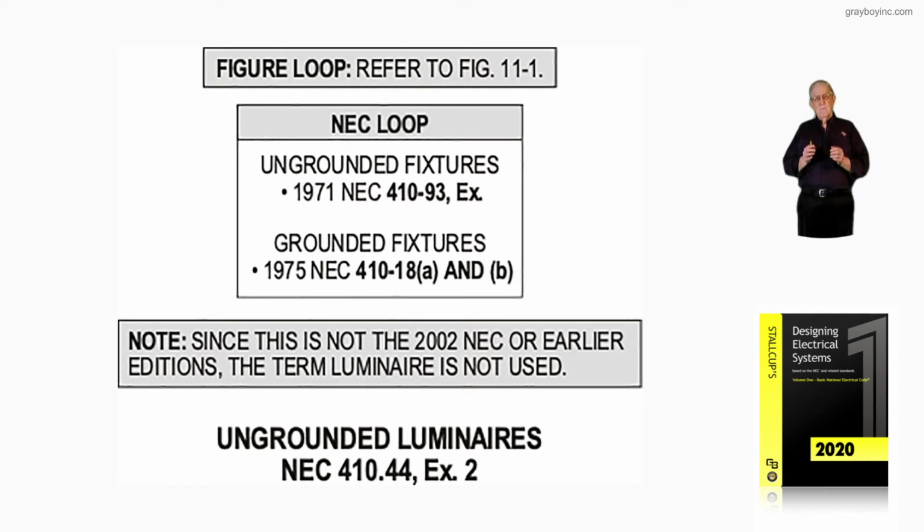So you can see that in past codes from 1971 and back, there were times when two-wire systems were run without an equipment ground and fixtures were installed. So this is the predicament that puts electricians in today when they're replacing lighting fixtures that are on a system that doesn't have an equipment ground routed with the ungrounded conductors. So these Figure 11-1 and 11-2 deal with such a condition.